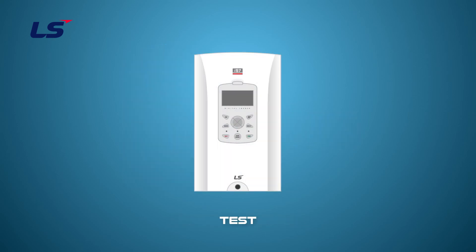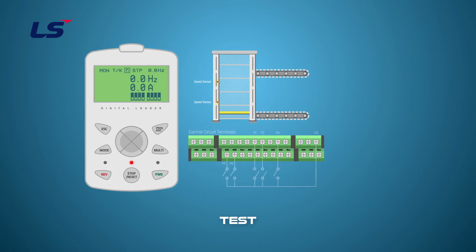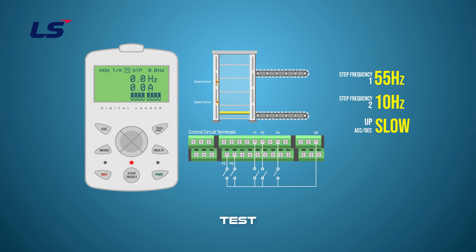Let's look at the sequence of the lift load according to the input status with a multi-step test. The rising motion is operated by forward operation, and the falling motion is operated by reverse operation. Step 1 of multi-step frequency is 55 Hz and step 2 is 10 Hz respectively. When the lift rises, we will apply the normal acceleration and deceleration time set by DRV3 and DRV4. When the lift falls, we will apply step 1 of multi-step accelerate-decelerate. The lift works by terminal inputs shown on the screen.